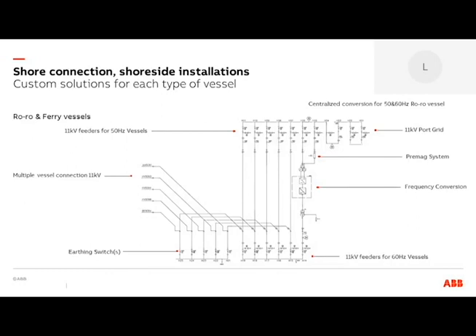5 minutes. Since all these vessels already have a transformer on board, and this transformer is already providing galvanic insulation, it's possible for this category of vessel to connect to the same bus bar. So in the picture here, we can see a centralized conversion that can deliver, for the vessel docking on the left side here, on this bus bar at 11 kilovolt, both 50 and 60 hertz. In this case, since the grid is already 11 kilovolt, the vessel will connect directly to the port grid.